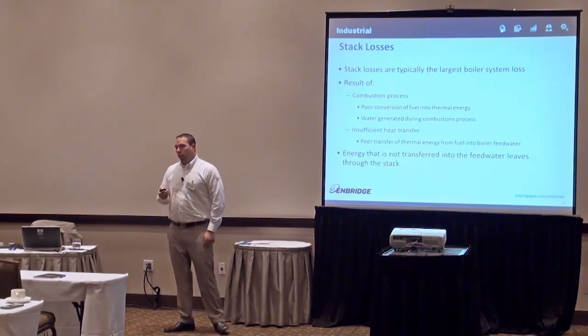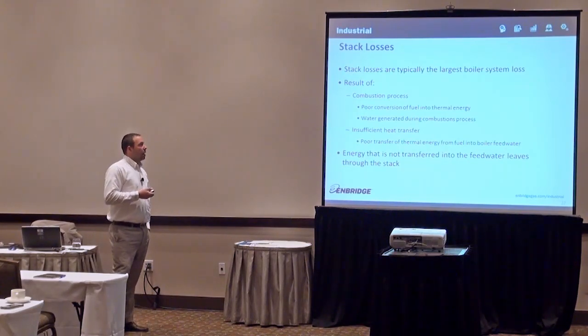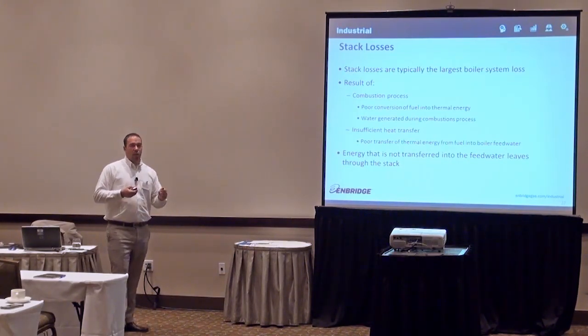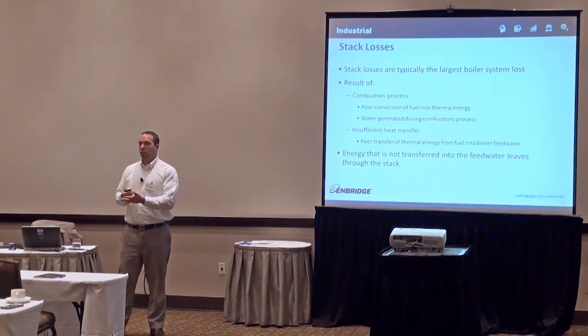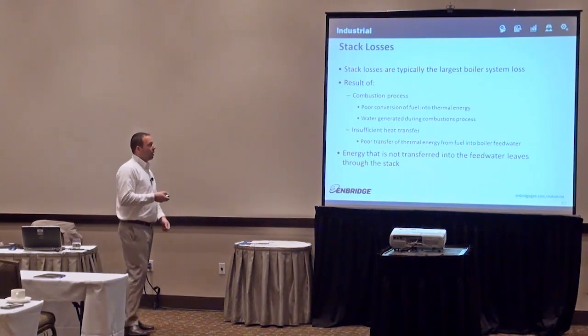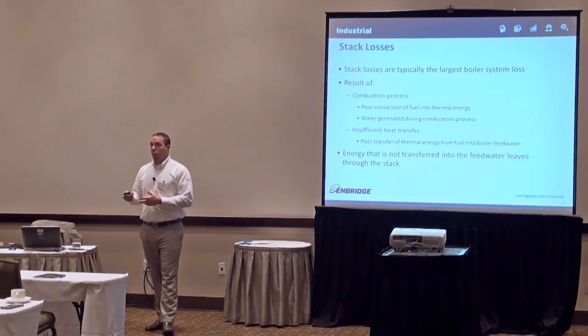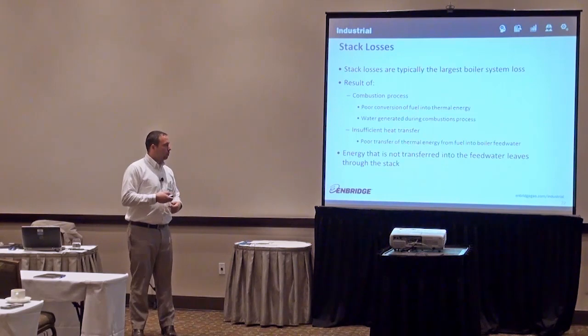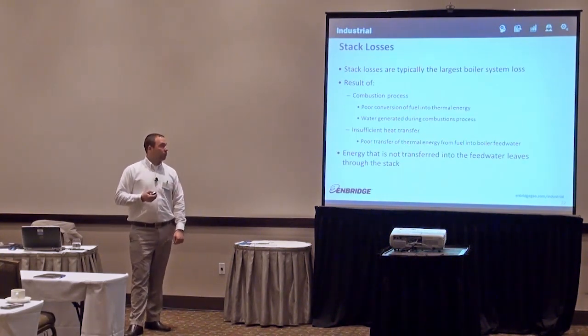Stack losses are a result of the combustion process. It can be that first handoff where we convert potential energy in the fuel into thermal energy. So if we have a poor handoff there, a poor conversion, we're going to have more losses. We also generate water during the combustion process.